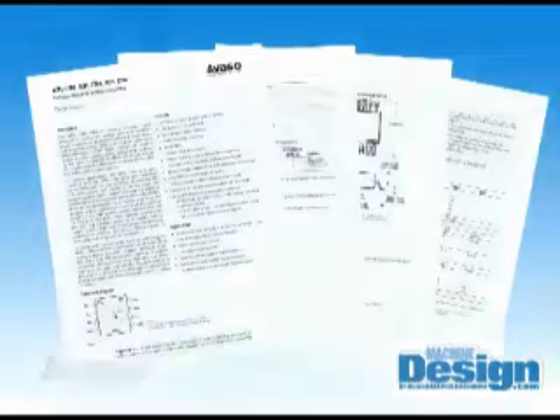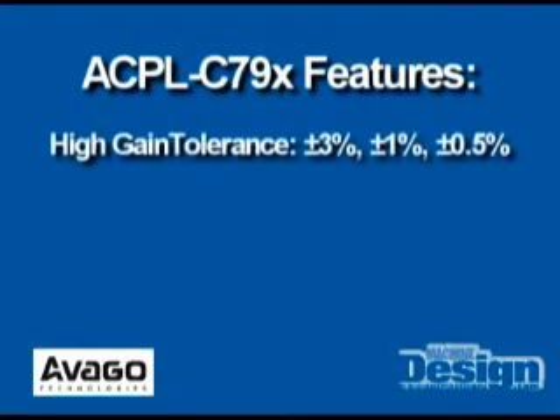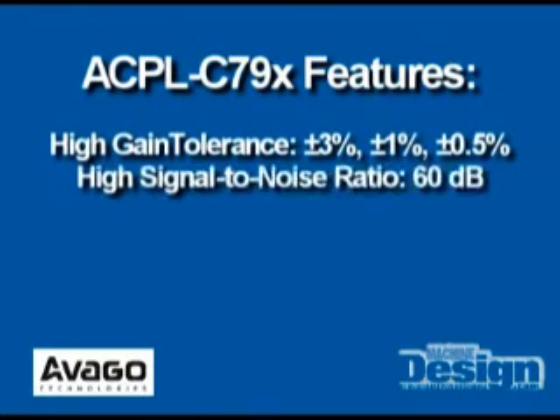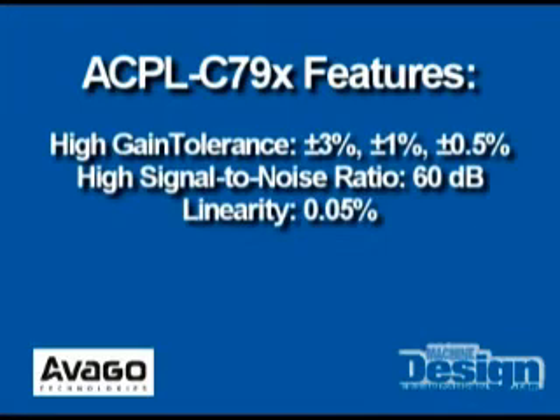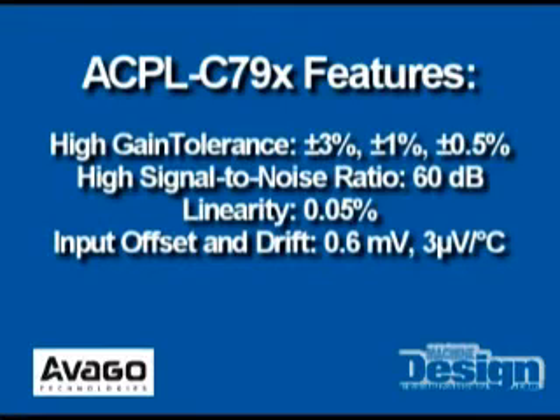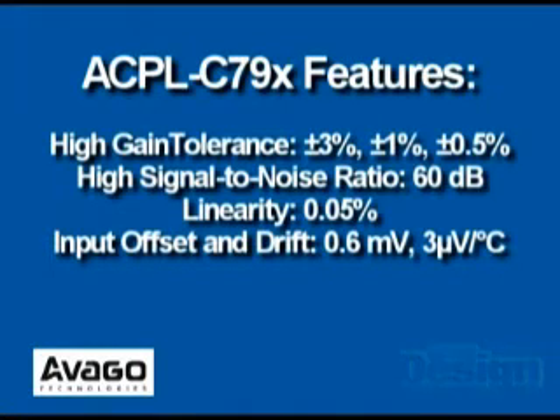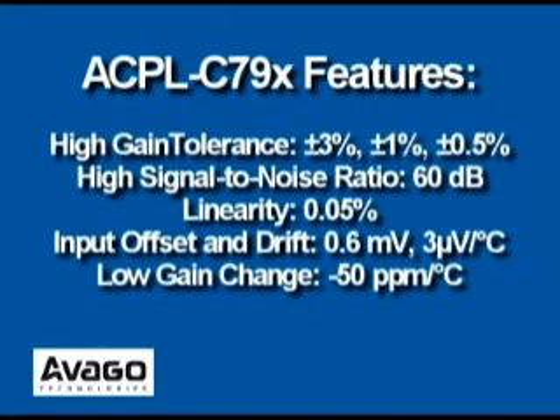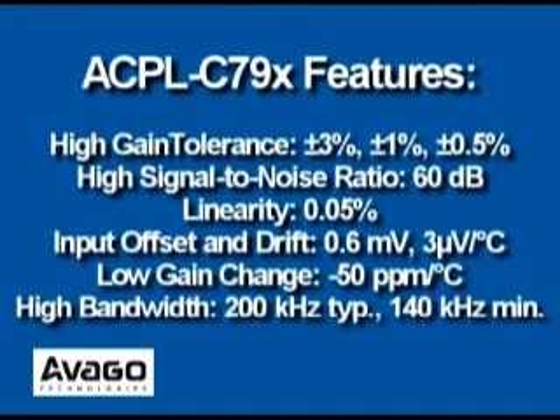Based on sigma delta analog to digital converters and chopper stabilized amplifiers, the new isolation amplifier features high gain tolerance options, high signal to noise ratio typically 60 dB, excellent non-linearity of 0.05%, low input offset voltage drift of 0.6 millivolts and 3 microvolts per degree Celsius, and low gain change versus temperature of negative 50 ppm per degree Celsius.